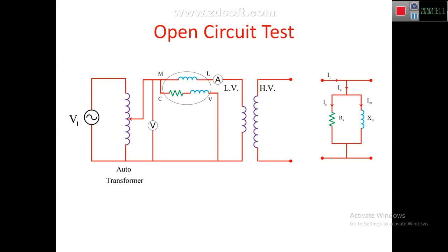All meters are connected on the LV side and the HV side is kept open circuited. In the equivalent circuit, the primary current I1 is divided into two components: exciting current IE and load component I1'. Since the secondary is open circuited, I2 equals zero, and therefore I1' is also zero. So I1 is exactly equal to the exciting current IE.